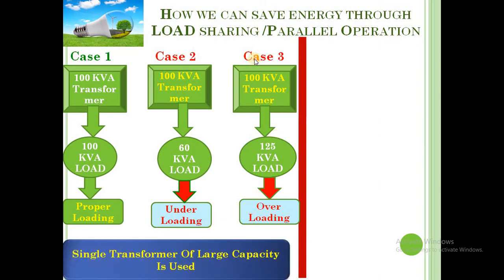But in case number 2, the load is less and the transformer rating is more. So in this case underloading will occur, and obviously underloading will cause reduced efficiency. Now in case number 3, a 100 kVA transformer is used and the load is 125 kVA, that is 25 kVA extra load we are putting on the 100 kVA transformer. So obviously there will be overloading. So in case number 2 and case number 3, there will be underloading and overloading situations, and because of these two there will be uneconomical operation of the transformer. Means the losses increase and the efficiency decreases.